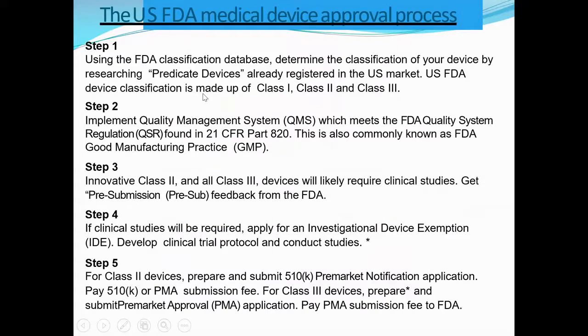So how do we register medical devices with the US FDA? We have to see in brief the regulatory approval process in the US FDA. What is step one? Step one is always that you have to classify. So you have to check the US FDA classification database to see which category your medical device falls under, the device for which you are going to take the marketing approval, register, and make the dossier. How will you find it?